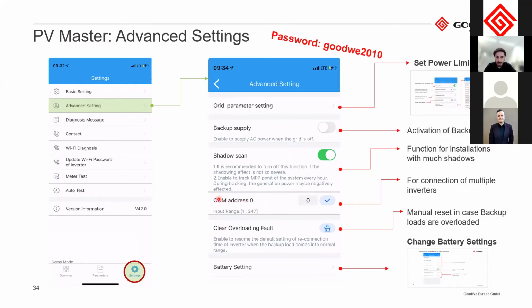The COM address here is in case you connect them in parallel, then you need to set the COM address for each inverter. That's unique. So you just enter it here. Clear overloading fault. This is in case you have a grid outage and you have connected too many loads to the backup output. Then the inverter will power down because of overloading. It will then try to restart after a fixed amount of time. And after doing this for a few times, it won't try to restart in case the load is still too much, and then you need to reset it manually. You just need to go in settings and click this one here. Here on the battery settings, let me show you.